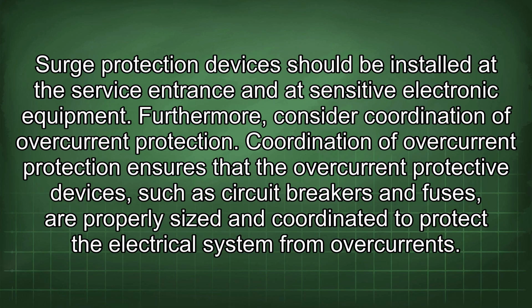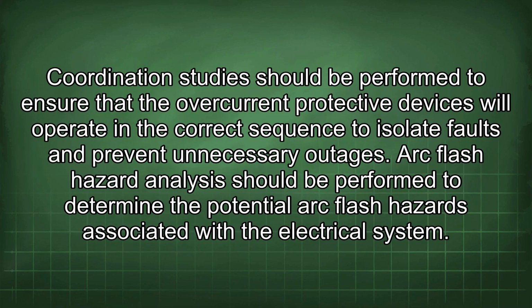Furthermore, consider coordination of overcurrent protection. Coordination of overcurrent protection ensures that the overcurrent protective devices, such as circuit breakers and fuses, are properly sized and coordinated to protect the electrical system from overcurrents. Coordination studies should be performed to ensure that the overcurrent protective devices will operate in the correct sequence to isolate faults and prevent unnecessary outages.